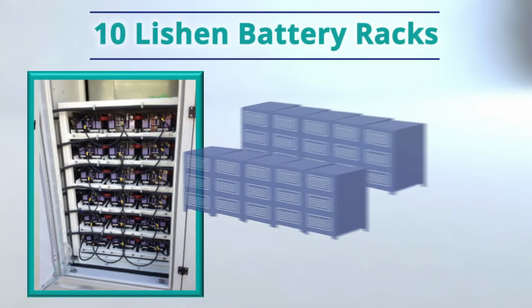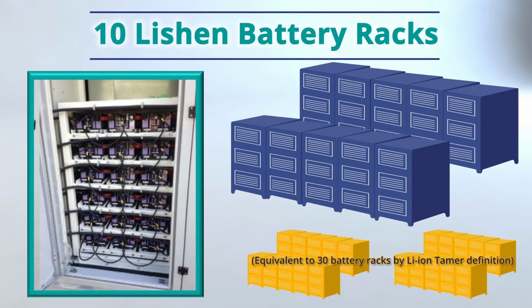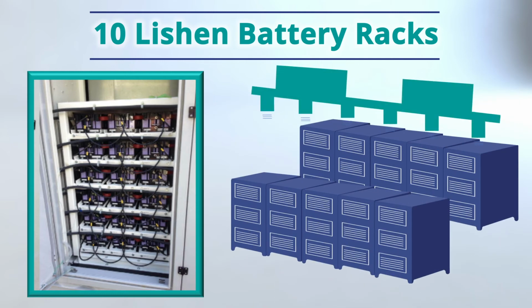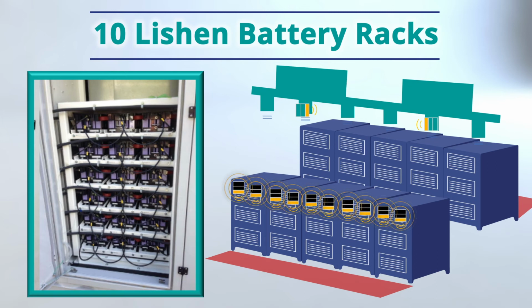Consider this cumulative example. There are 10 Lishen battery racks, equivalent to 30 battery racks by our definition. 2 HVAC supply points, so reference sensors will be mounted here. No personnel entry points. Hot aisles located near walls of the container, so monitoring sensors will be mounted here. And cold aisle located in the center of the container.